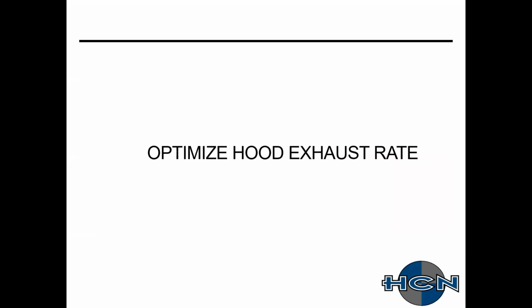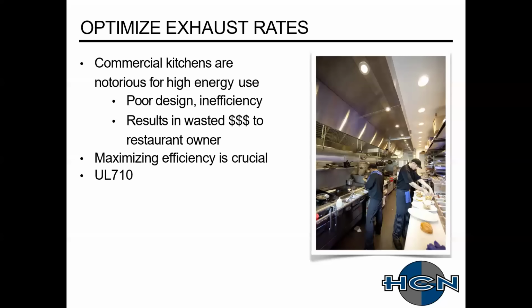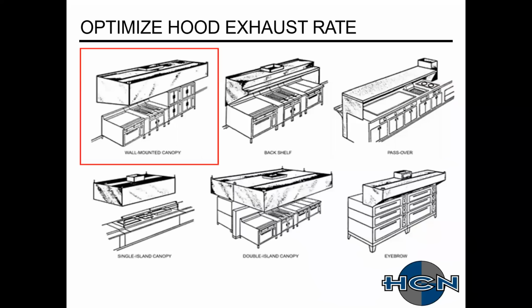So optimizing your hood exhaust rate. As we stated, commercial kitchens are notorious for high energy use. They're big on efficiency, but a lot of it is poor design. So we want to maximize that efficiency as best as we can. And your best bet for doing this is using a listed product. And depending on where you are in the US, a lot of jurisdictions require listed hoods, not all do. So when we're talking about hoods, there's a lot of different variations of hoods. And your hood selection is really going to be based on what kind of cooking equipment you have to cover. You want to use the best hood you can to cover that equipment appropriately.